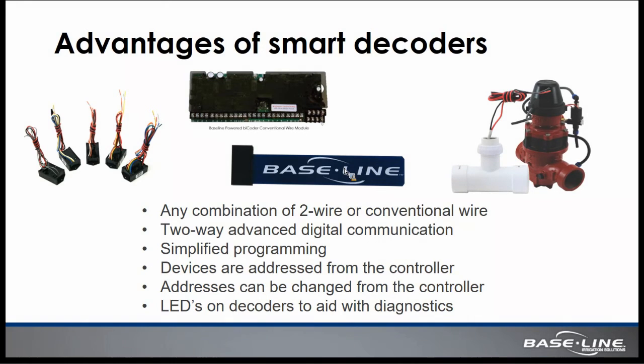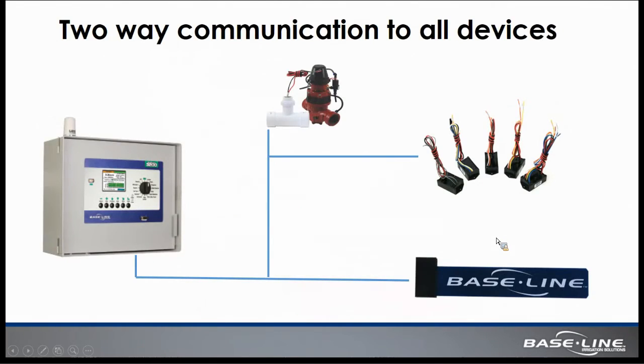And because of that two-way advanced communication, it can simplify the programming in that the devices are addressed from the controller, or they can be changed from the controller, so that it makes it easy for the contractor to set the system up. So we're going to focus really on two-way advanced digital communication and the advantages of that as it relates to a 2-wire system.